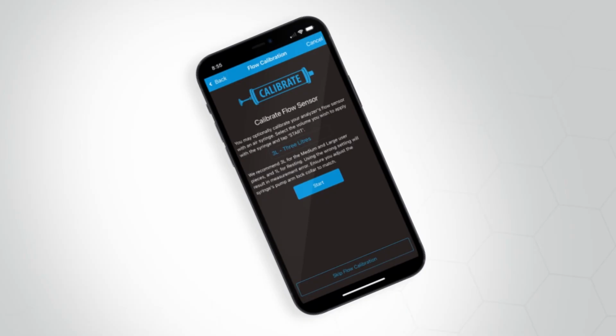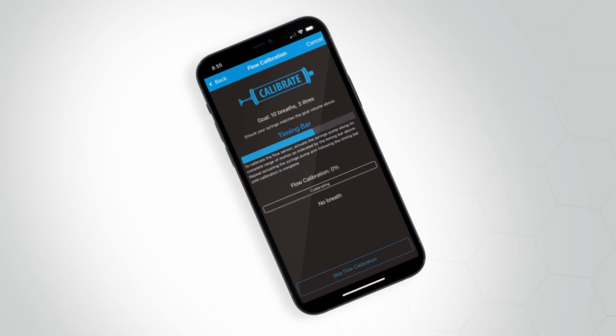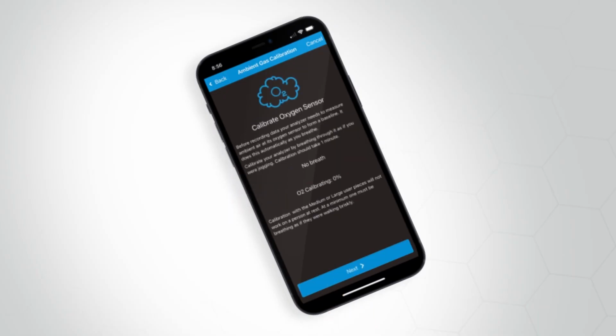Confirm the set volume for the calibration syringe and tap the Start button to initiate the first part of the calibration process. Once completed, you will continue to the final part of the oxygen sensor calibration process. Follow the calibration instructions for each step provided within the app.